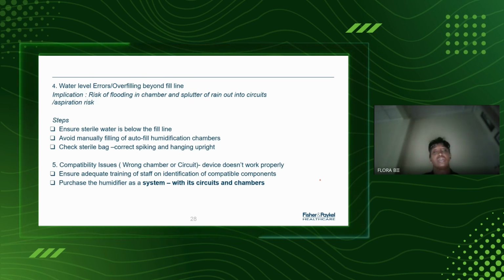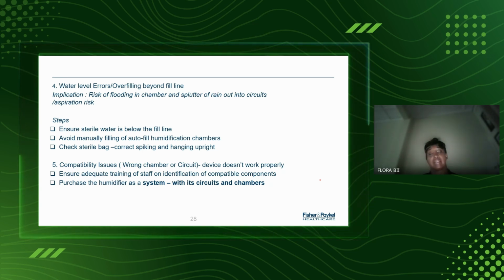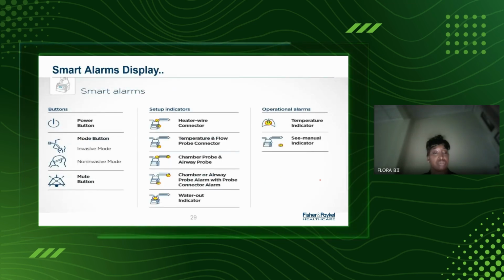So water levels, this is also just making sure that you have water in the water bags, which would be drawing in. So you'd ensure that you'd be checking that the sterile water is one below the fill line. Please try not to manually fill auto-fill humidification chambers. There are some that just draw as much water as they require, but also just check that as you purchase these humidifiers, you're purchasing them as a system in terms of compatibilities of the humidifier itself with its own circuit and chambers, preferably from the same manufacturer, so that it's easier to troubleshoot in case issues do arise.